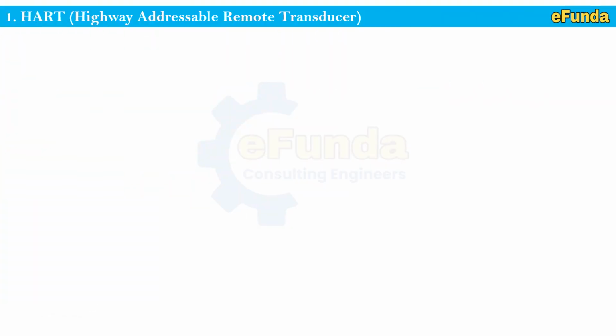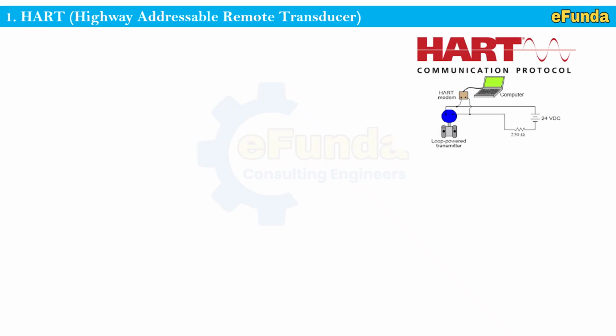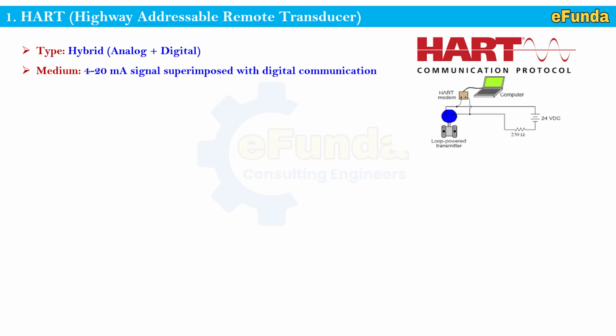First, HART, Highway Addressable Remote Transducer. One can refer to the HART communication protocol symbology, where a loop powered transmitter is connected to the computer via a HART modem, with the power supply and a 250 ohm resistor connected to the transmitter. Type: hybrid, analog plus digital. Medium: 4 to 20 milliamp signal superimposed with digital communication. Speed: 1.2 kilobits per second. Topology: point to point or multi-drop.